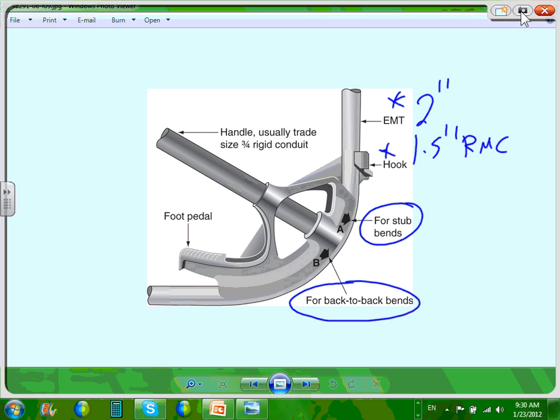These are good applications for 1/2, 3/4. You go to 1 inch, you're almost there, but you go higher than 1 inch, it really doesn't pay for a lot of companies to bend them in the field. They pre-manufacture them already bent, EMT or rigid. Just takes too much time.